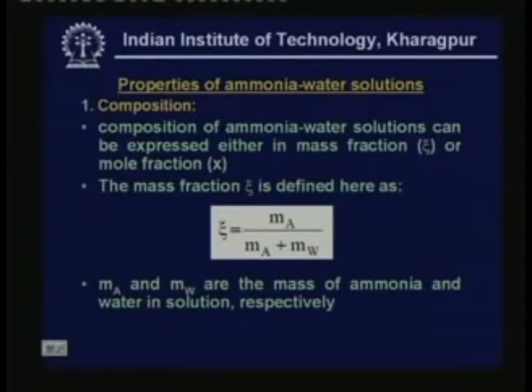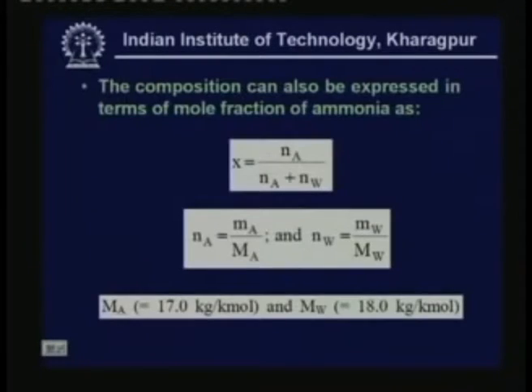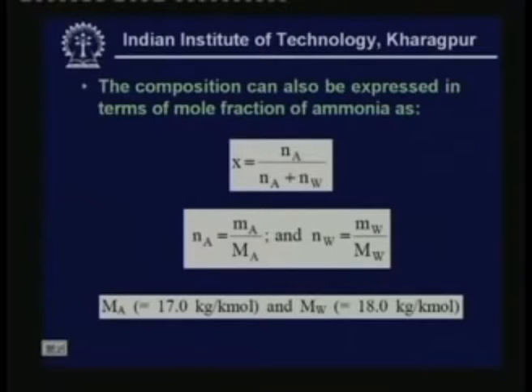The mass fraction ζ is defined as mass of ammonia M_A divided by the total mass of the solution, M_A plus M_W, where M_A and M_W are masses of ammonia and water respectively. Similarly, the liquid phase mole fraction X is defined as the number of moles of ammonia in the liquid phase divided by the total number of moles in the liquid phase. The number of moles of ammonia N_A equals mass of ammonia divided by molecular weight of ammonia, and for water similarly. For calculation purposes, take molecular weight of ammonia as 17 kg/kmol and molecular weight of water as 18 kg/kmol.